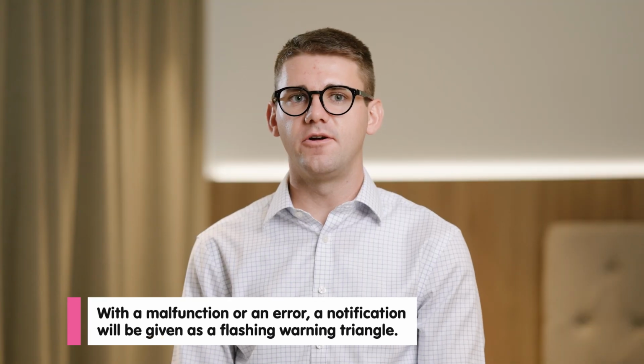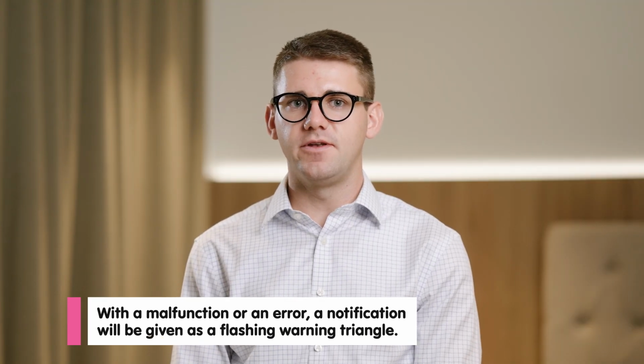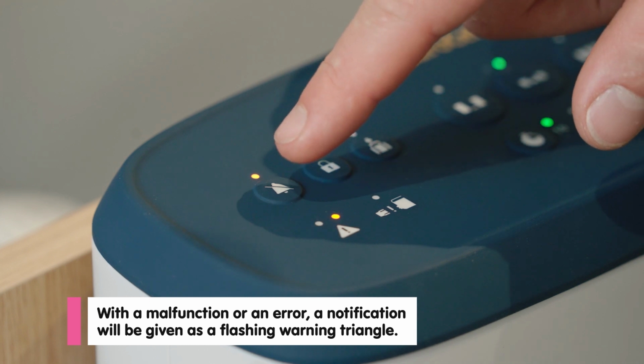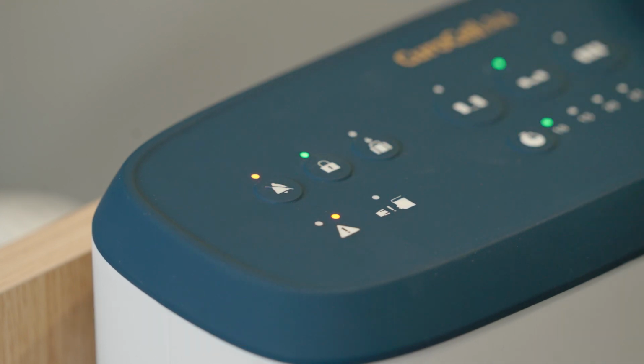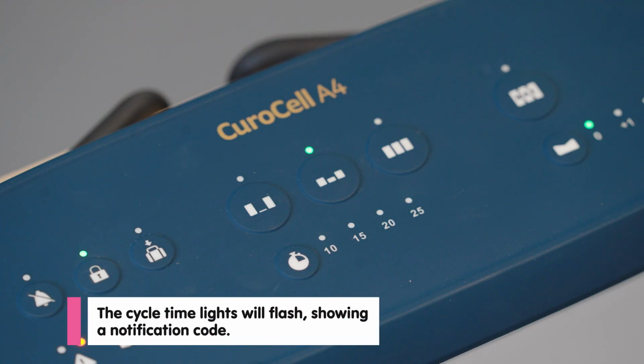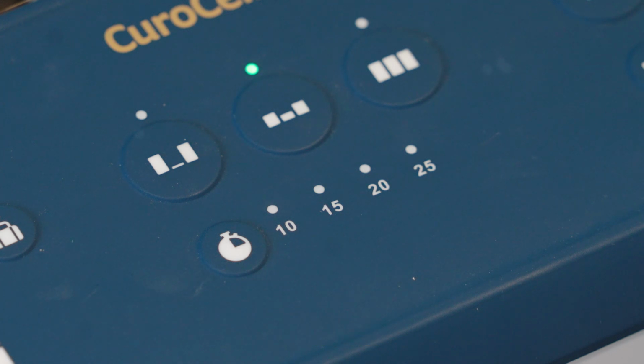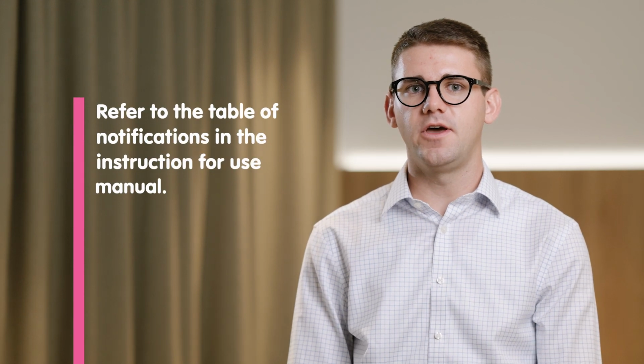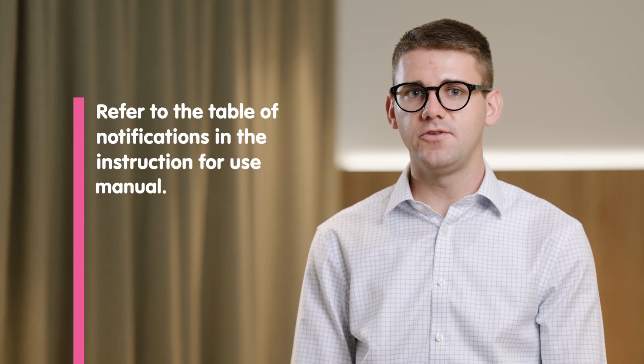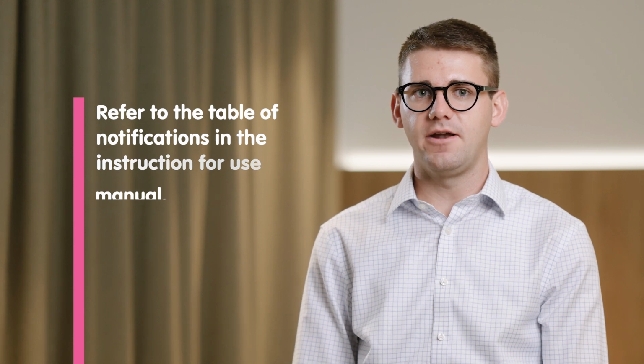With a malfunction or an error, a notification will be given by way of a flashing warning triangle. To mute the warning signal, press the mute button. When a notification occurs, the cycle time light will flash and a notification code is shown on the 4 different cycle time lights: 10, 15, 20, 25. You can refer to the table of notifications in the instructions for use manual for full detail about the error code. The error code will remain and be displayed until the error has been rectified.